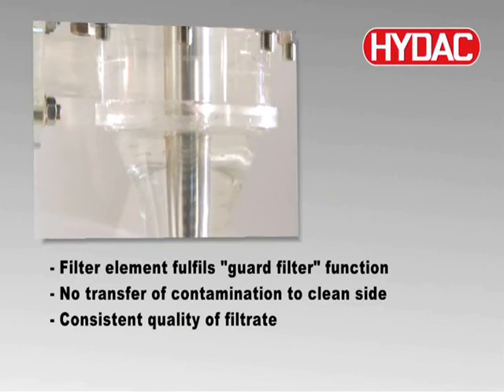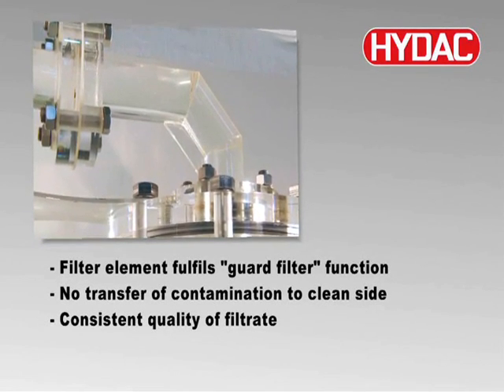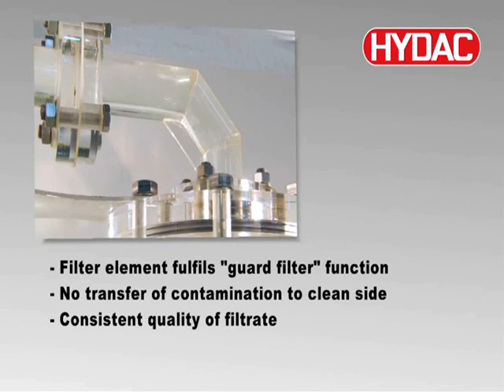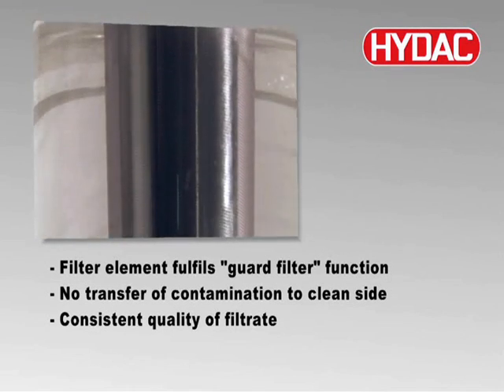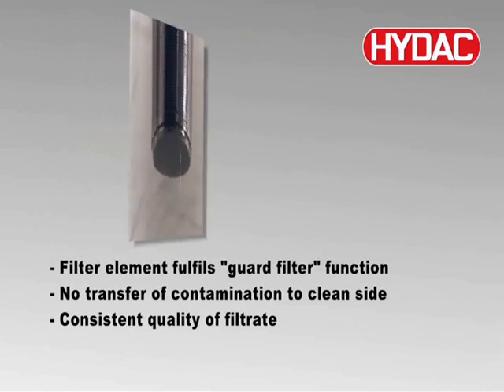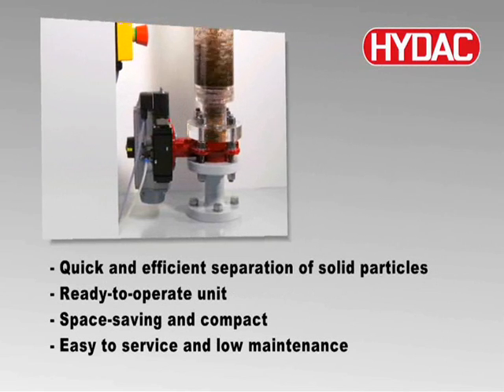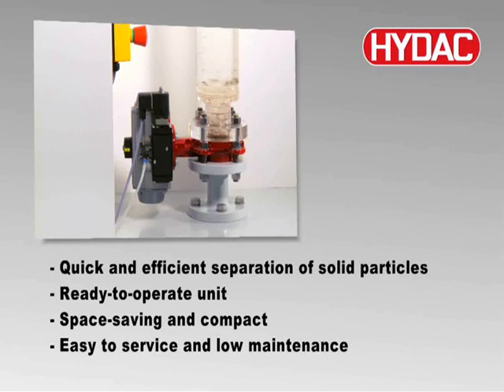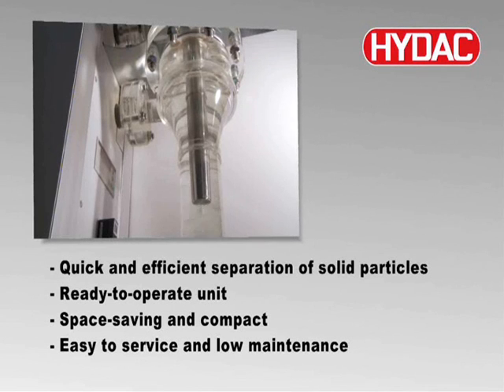In contrast to a conventional centrifugal separator, the assured separation efficiency of the HYDAC Auto-Filt Twist Flow Strainer does not depend on the operating conditions, but on the filtration rating of the filter element. This guarantees that the ATF produces filtrate of consistent quality, even during concentration surges or fluctuations in operating pressure or flow rate. In comparison to inclined plate clarifiers or sedimentation basins, the HYDAC Auto-Filt Twist Flow Strainer, with its low space requirement, separates solid particles far more rapidly and efficiently.